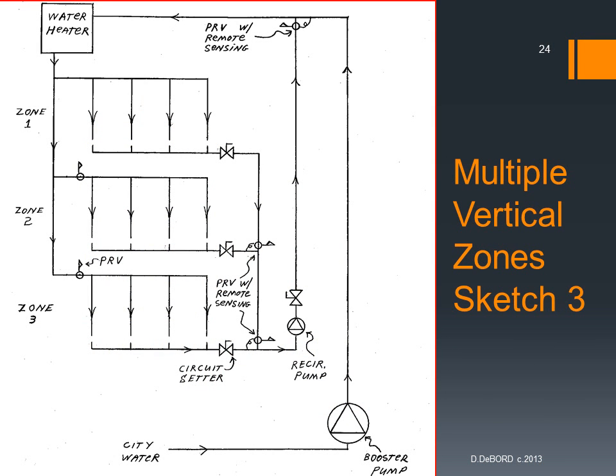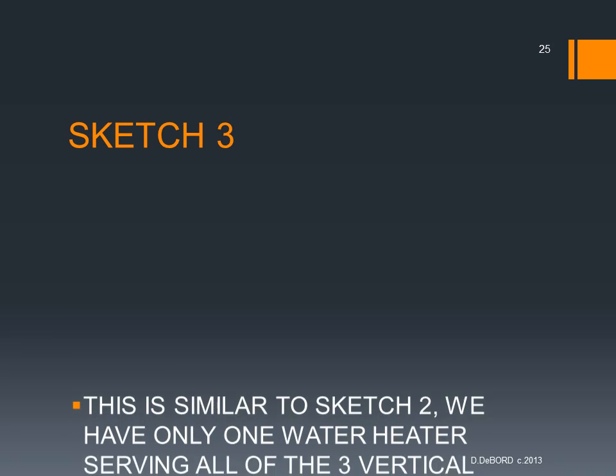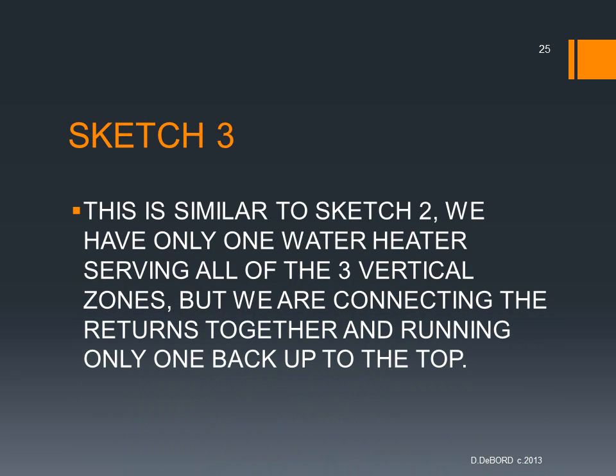Here's sketch 3. Again, we have one water heater and it's feeding all the zones, and we have a PRV for zone 2, PRV for zone 3, and then we have PRVs on the backside, the remote sensing piloted valves to balance, because you're going to have different pressures as they connect back together. And then you have one recirc pump at the bottom feeding up, and you have a PRV at the top again. So let's take a look at that again.